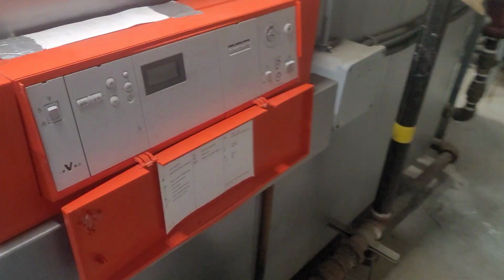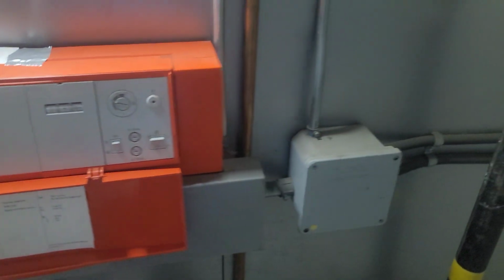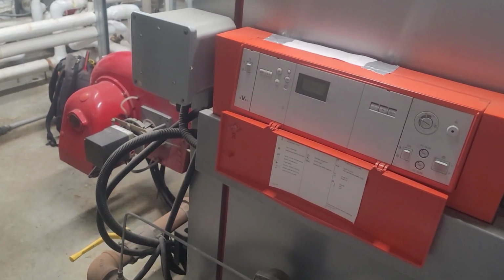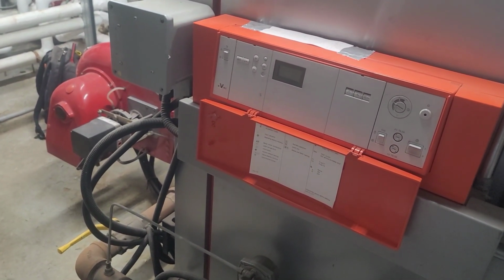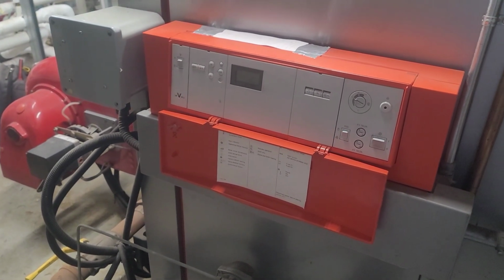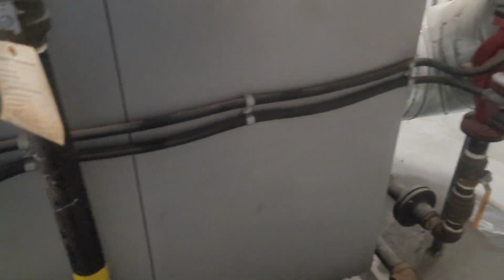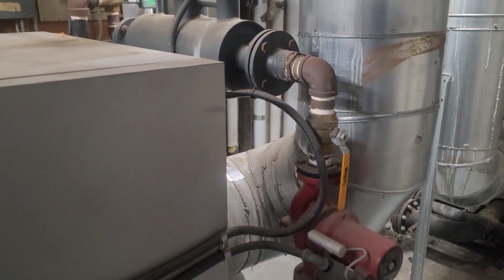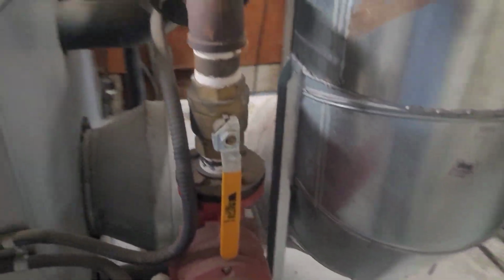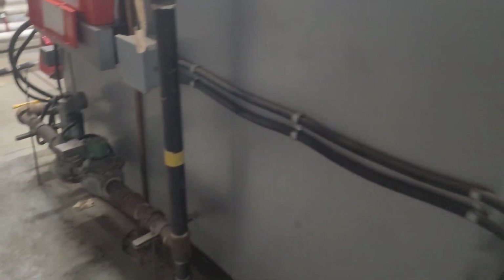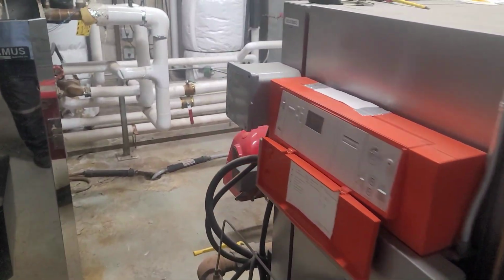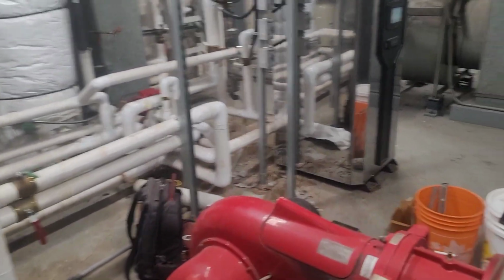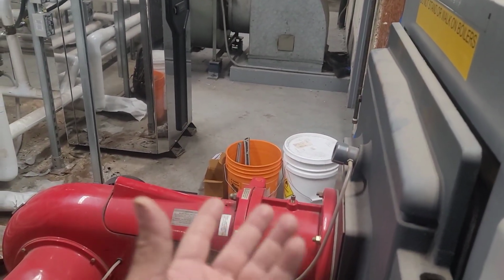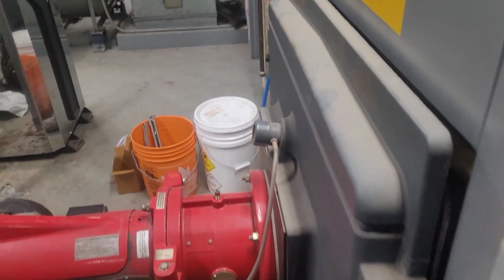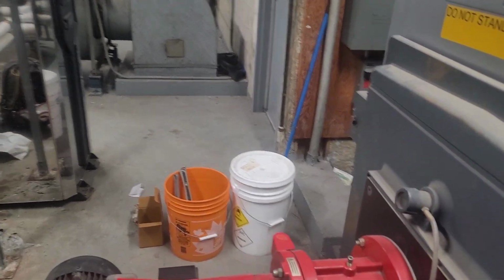So this is the main control board. Right now the boiler is not in working condition because of the summer, and we're gonna turn them on, I think, within this month. Before that we performed a full cleaning on this boiler, and during the cleaning I found the burner plate, or you can call it a diffuser, and the burner that had a crack on the surface.